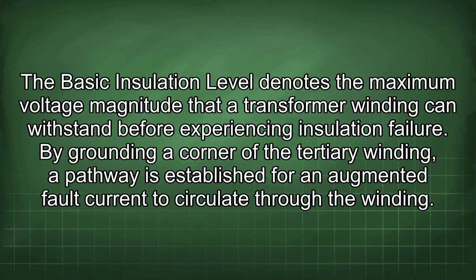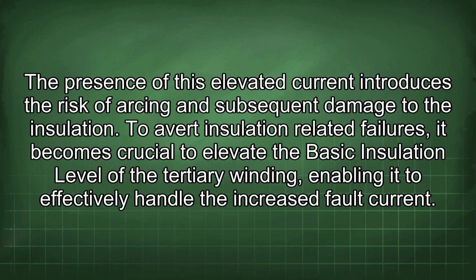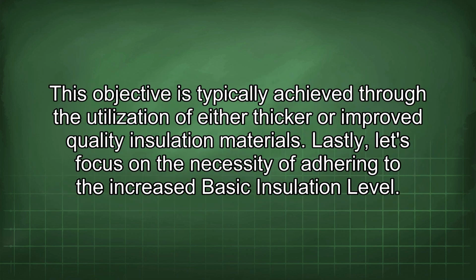The basic insulation level denotes the maximum voltage magnitude that a transformer winding can withstand before experiencing insulation failure. By grounding a corner of the tertiary winding, a pathway is established for an augmented fault current to circulate through the winding. The presence of this elevated current introduces the risk of arcing and subsequent damage to the insulation. To avert insulation-related failures, it becomes crucial to elevate the basic insulation level of the tertiary winding, enabling it to effectively handle the increased fault current. This objective is typically achieved through the utilization of either thicker or improved quality insulation materials.